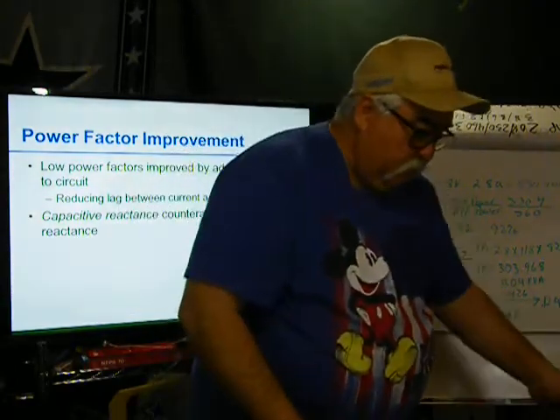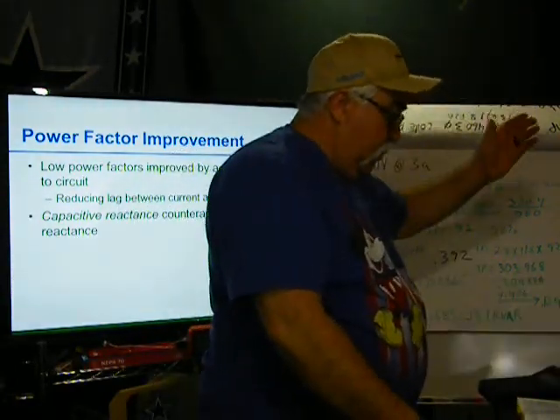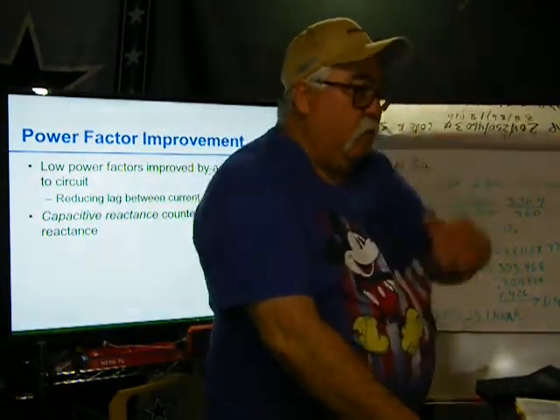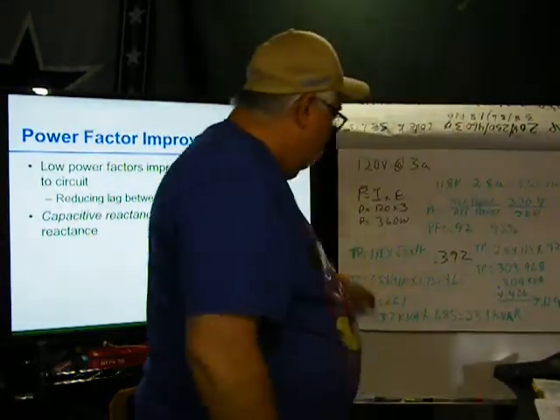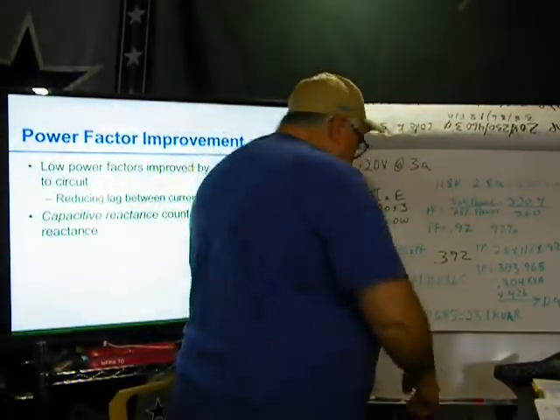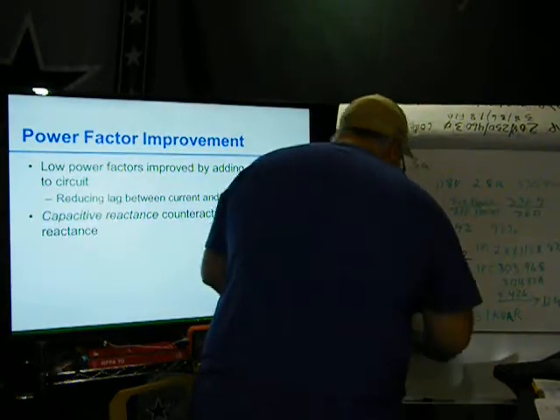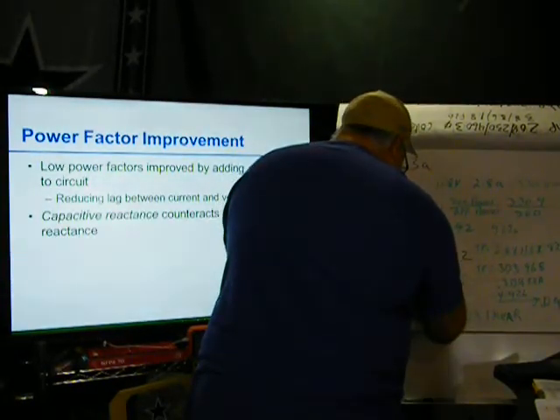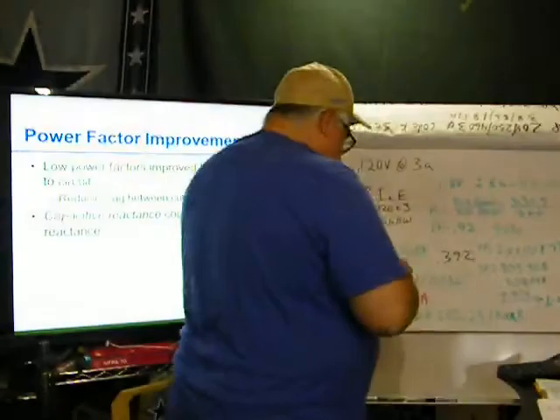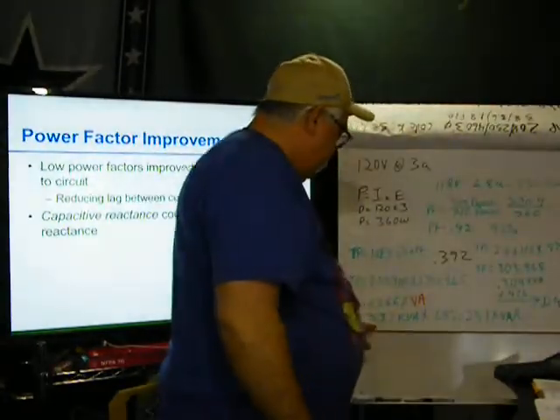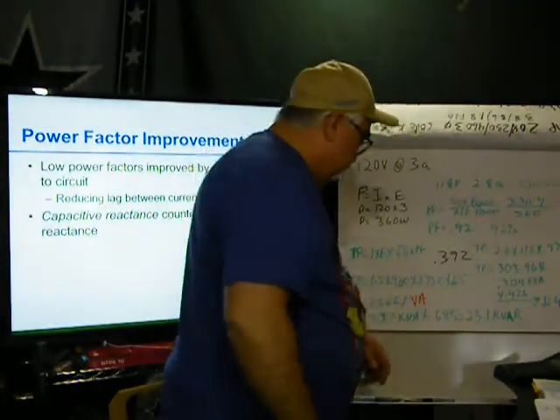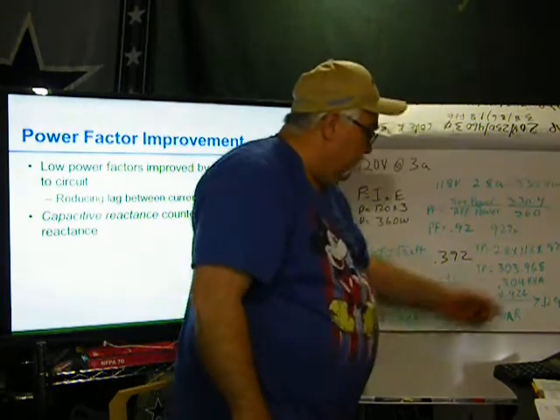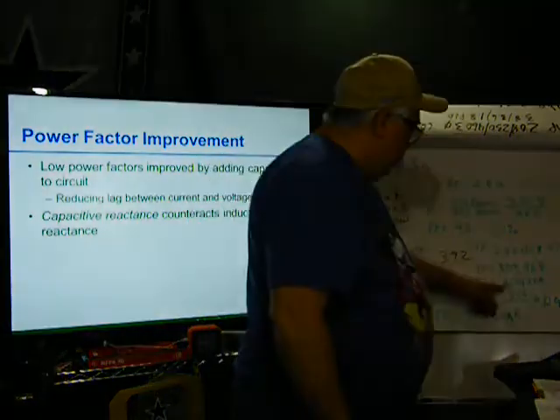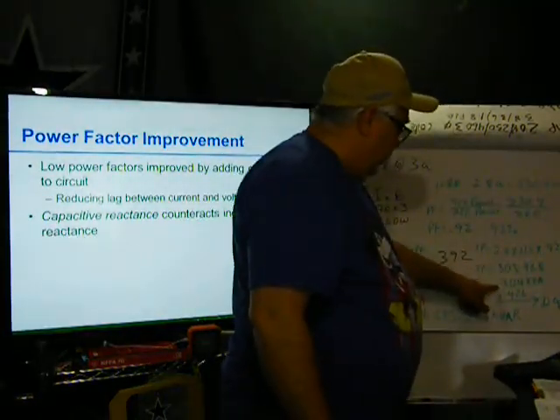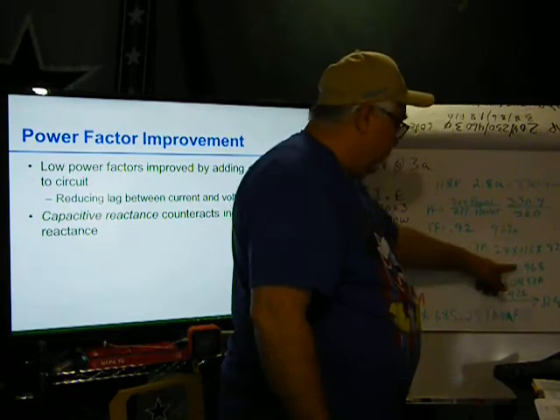Okay, so it's using the table. Look on the left, where are you? Then go across, and that is your multiplier. Your multiplier, you're going to multiply it by your kVA. Okay, this is my VA. Down here it says K because I knocked it from 33,601. I rounded off. Same thing over here. Because it's less than 1,000. That's why the decimal points here. That's less than 1,000.